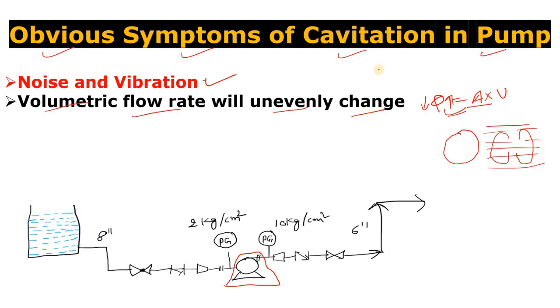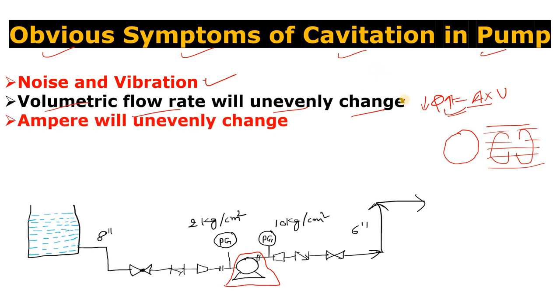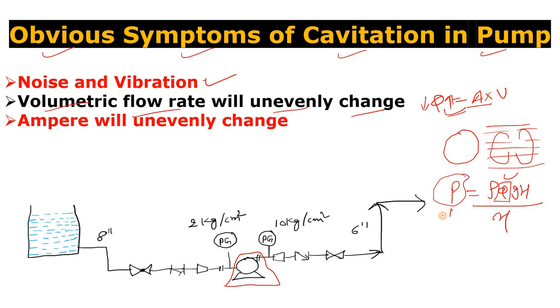The next symptom is that the ampere will unevenly change. The power for the centrifugal pump is rho times Q times g times H divided by efficiency. Since Q unevenly changes, power will also unevenly change, and therefore the ampere will also unevenly change. You have to check the ampere as well from the LCS.